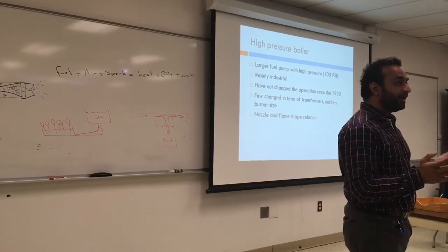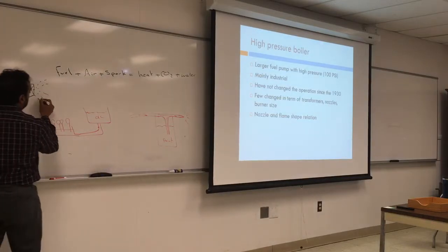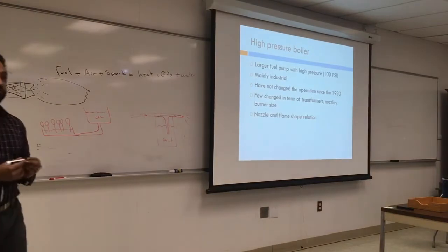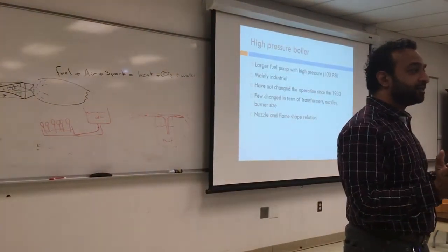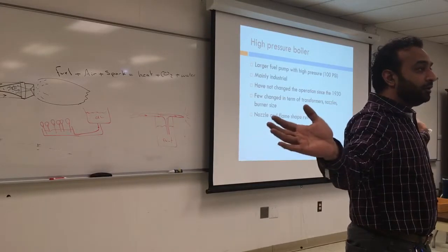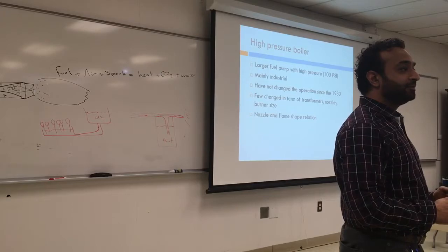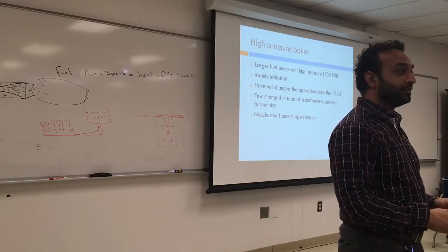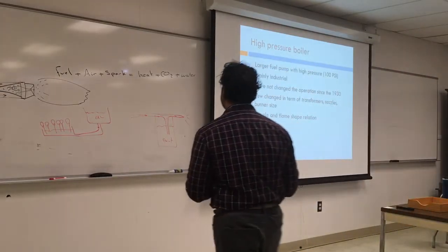So the way we spray the oil will define the cloud and the amount of flame we have. We want the flame as contained as possible. We don't want it to be spread out. You don't want the flame to be touching any wall in the chamber. Keep that in mind. If it's touching the wall, something is wrong. You're going to have some kind of smoke. So you want the flame to be inside the chamber.